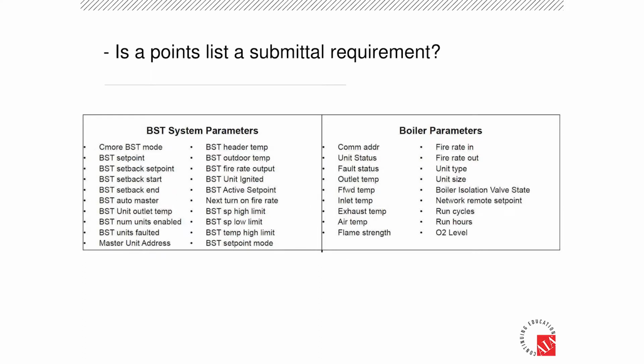So again, when we're reviewing these, who's controlling what? It needs to be clear. And those are key things that we want to look at when we're doing design review. Again, this is what we're wanting to see. We're starting to ask for this now in the specifications and asking the owner and the designers to put in a requirement to add these parameters. So this was a pretty extensive integration points list that came from the boiler manufacturer, which was very helpful. Still didn't give me what I wanted, which is what's read-only versus what's writable. But it was a start.